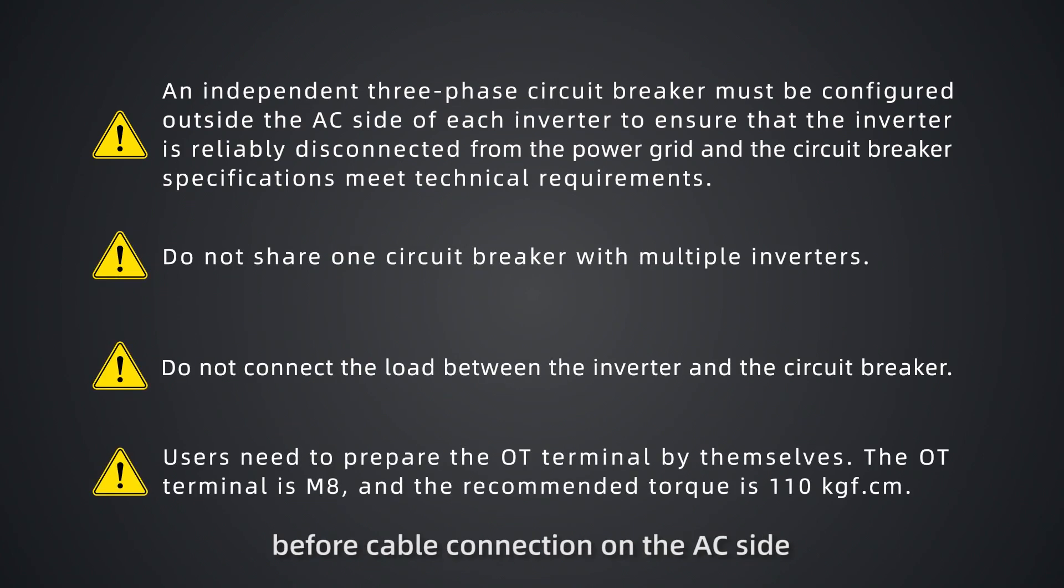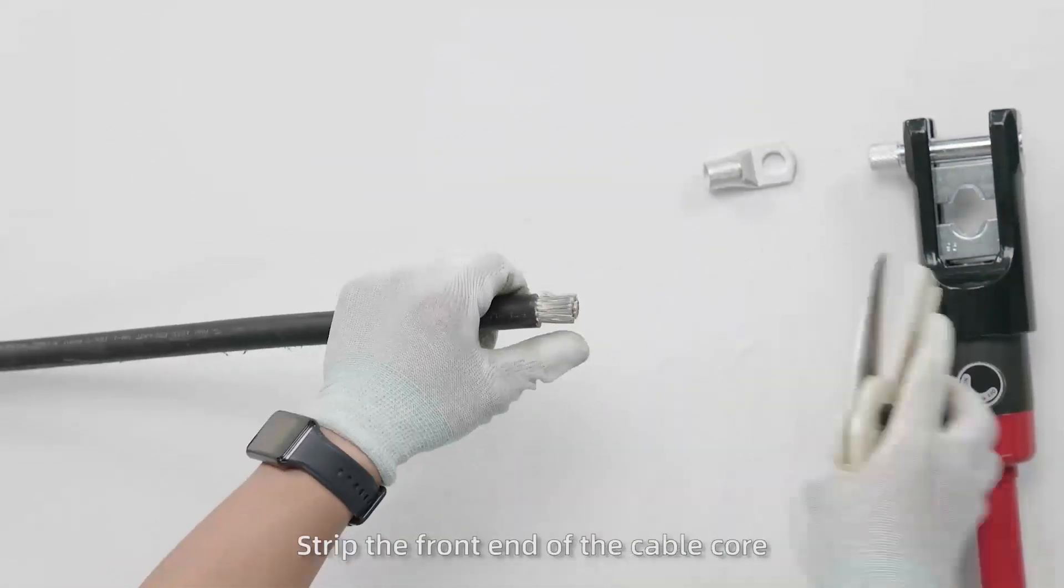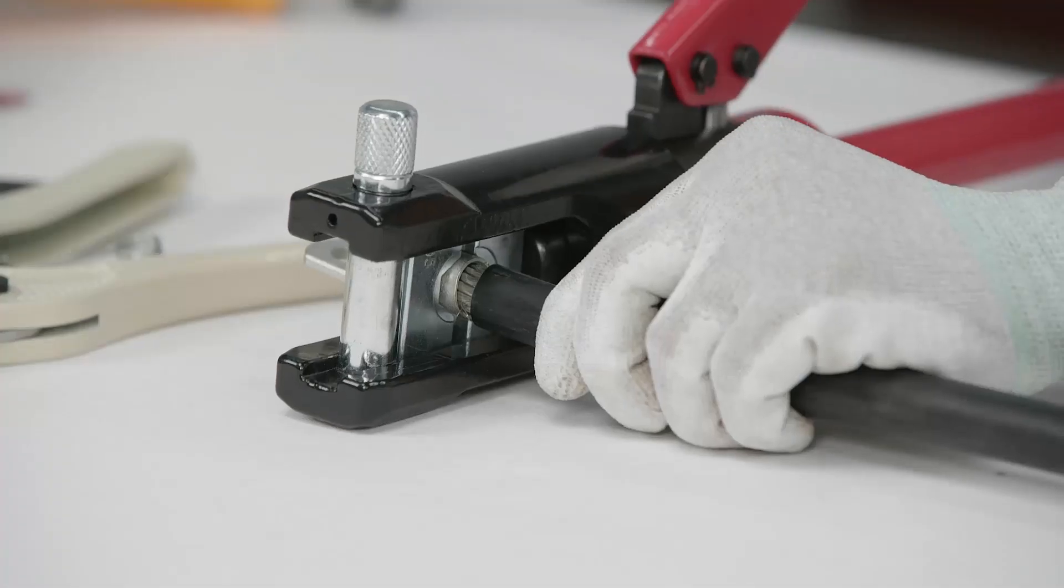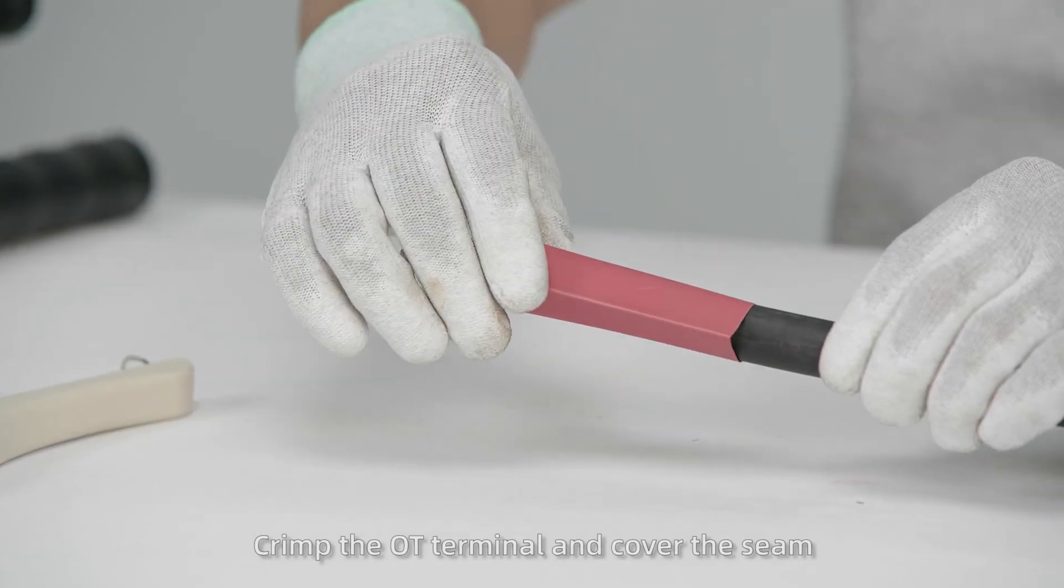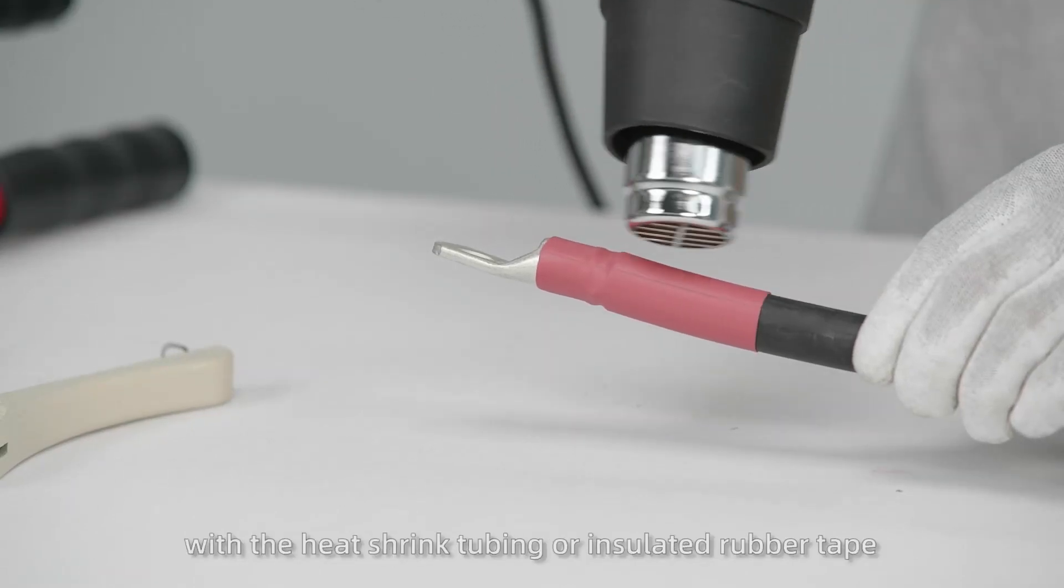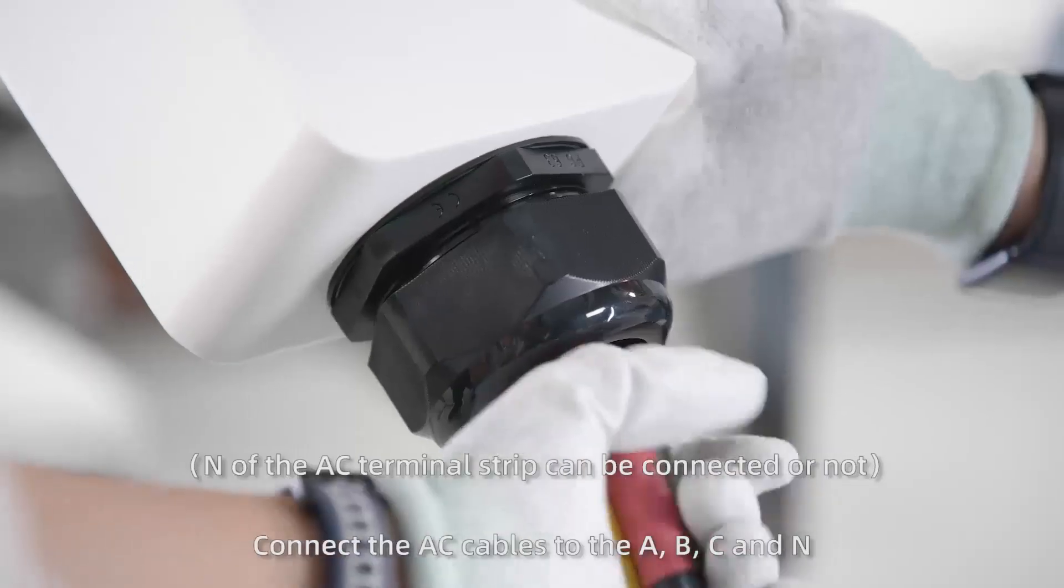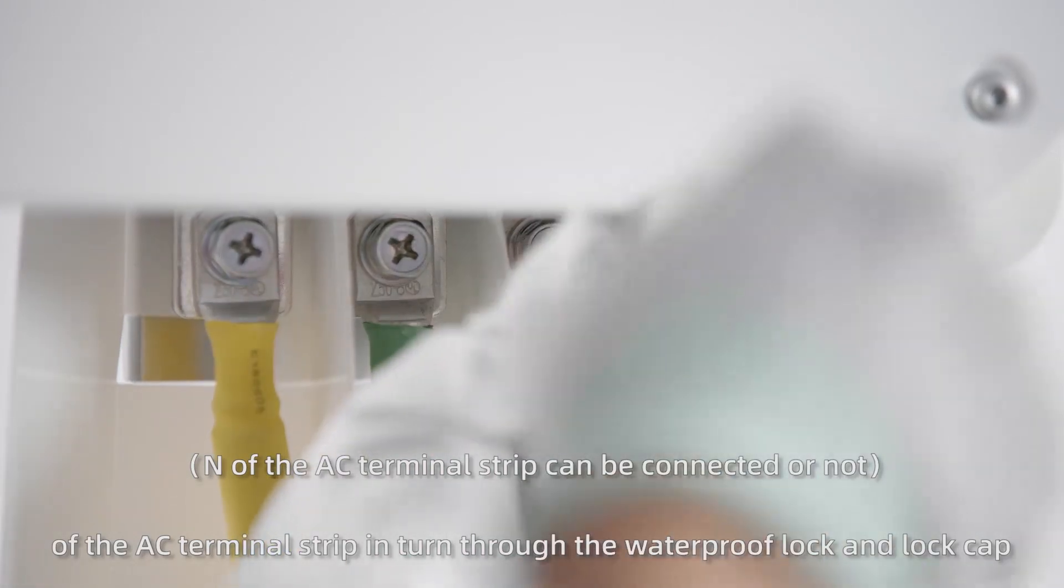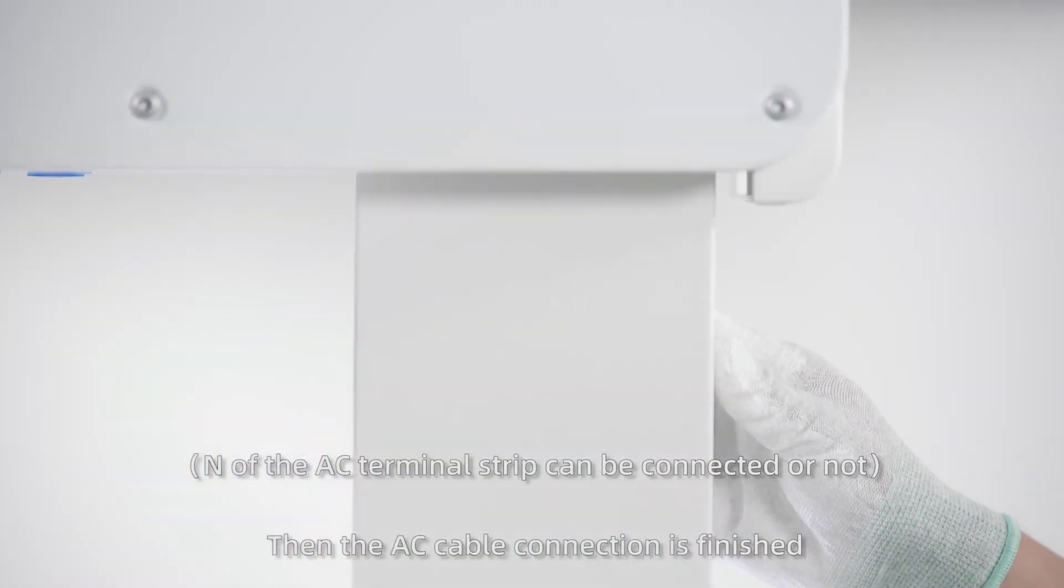Then, connect cables on the AC side. Pay attention to the above precautions before cable connection on the AC side. First, make the OT terminal. Strip the front end of the cable core. Crimp the OT terminal and cover the seam with the heat shrink tubing or insulated rubber tape. Then install the waterproof lock and unscrew the lock cap of the waterproof lock head. Connect the AC cables to the A, B, C, and N of the AC terminal strip in turn through the waterproof lock and lock cap. Reinstall the AC cable cover and tighten the lock cap. Then the AC cable connection is finished.